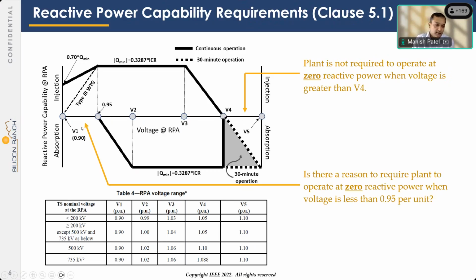So then if you apply the same rationale and come to the other side of the figure where the voltage is less than 95%, all the way down to 90%, because there is no slanted line like this up here, what this means is the plant shall be capable to operate at 0 reactive power output when voltage is less than 95%. Anyhow, just engineers thinking here, what could be the system scenario where the plant needs to operate at 0 reactive power output when the voltage is less than 95%? They would want the plant to inject reactive power into the system so that it helps boost the voltage above 95%. So anyway, something to think about for the next working group revising this standard.